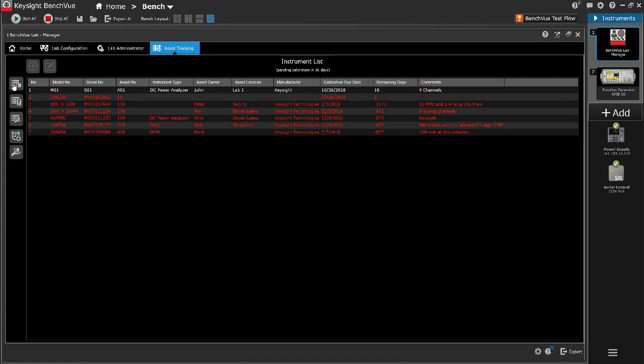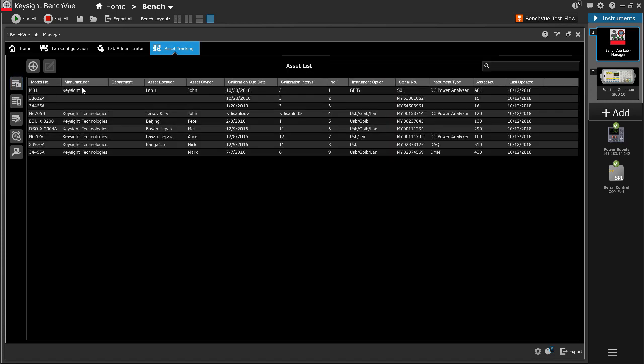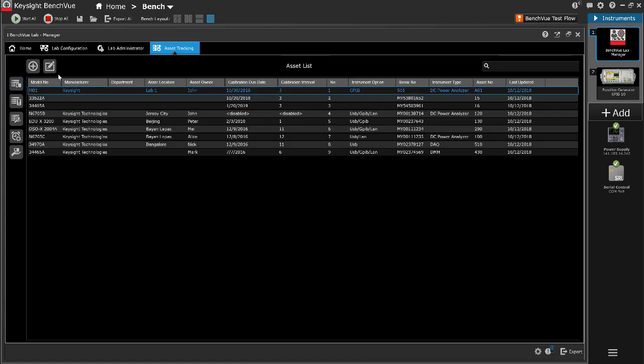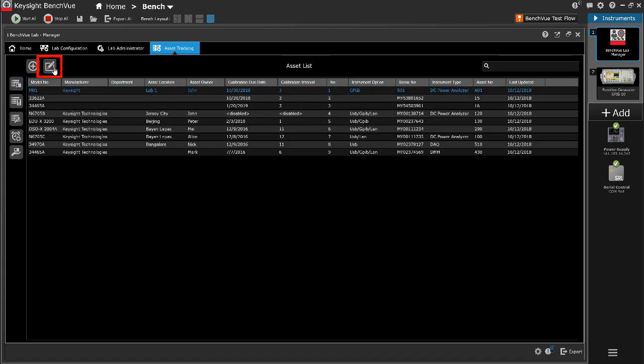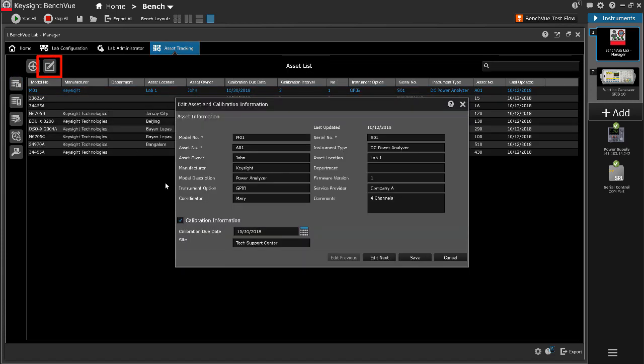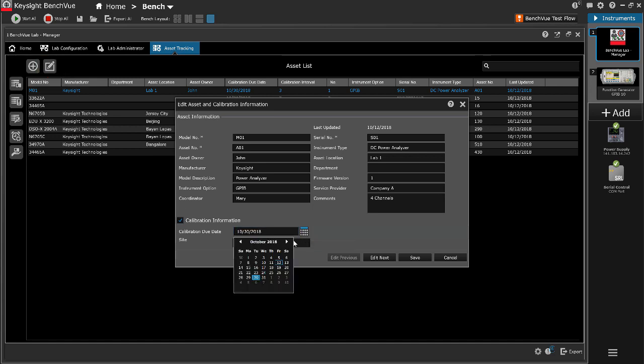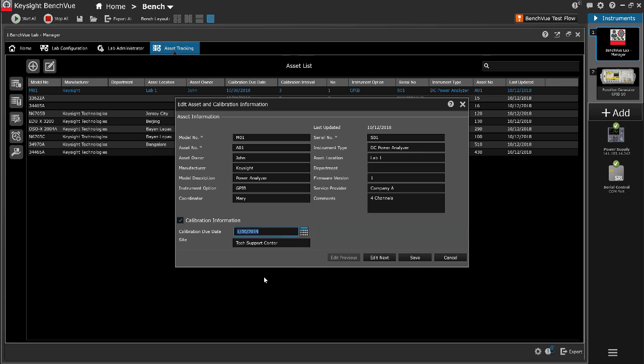After calibration has been completed, click the Edit Asset icon on the selected instrument to update the calibration due date. The system will automatically track the next recurrent calibration due date.